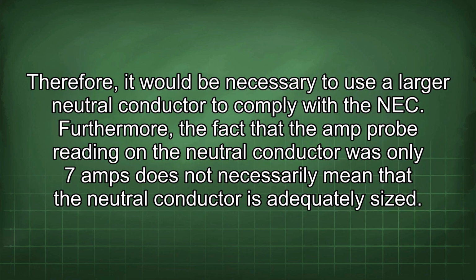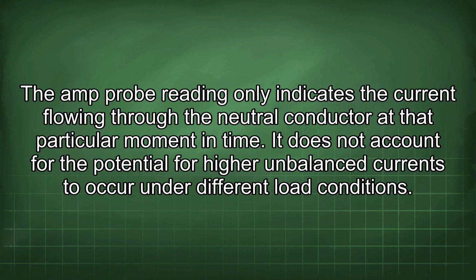Therefore, it would be necessary to use a larger neutral conductor to comply with the NEC. Furthermore, the fact that the amp probe reading on the neutral conductor was only 7 amps does not necessarily mean that the neutral conductor is adequately sized. The amp probe reading only indicates the current flowing through the neutral conductor at that particular moment in time. It does not account for the potential for higher unbalanced currents to occur under different load conditions.